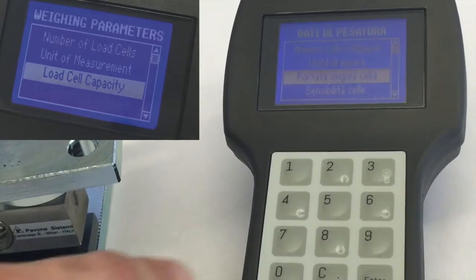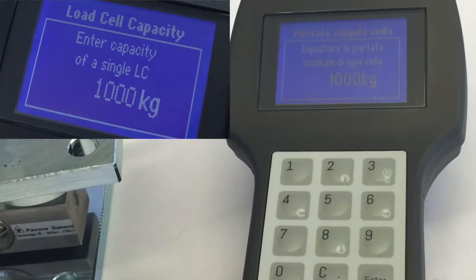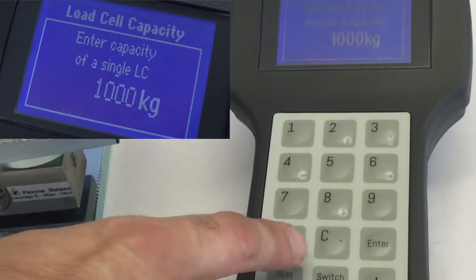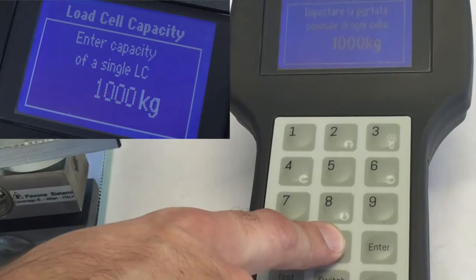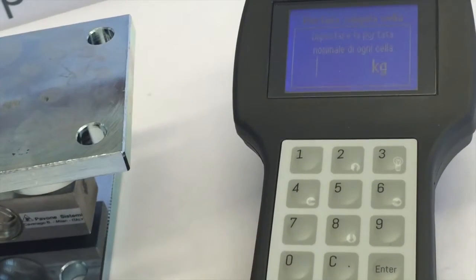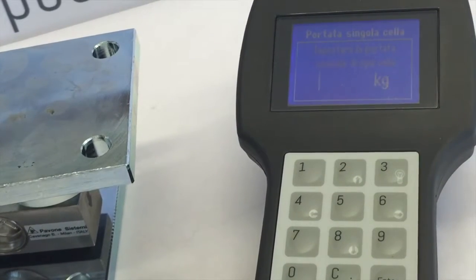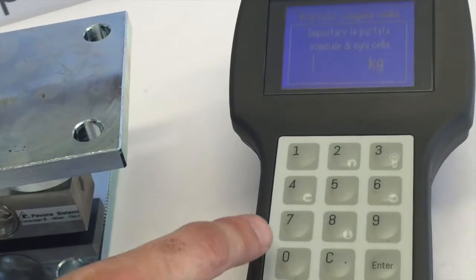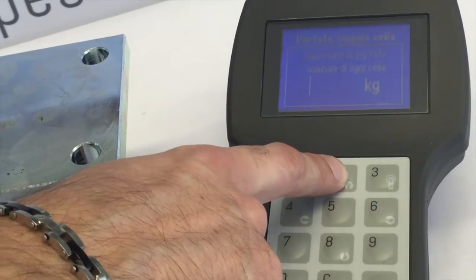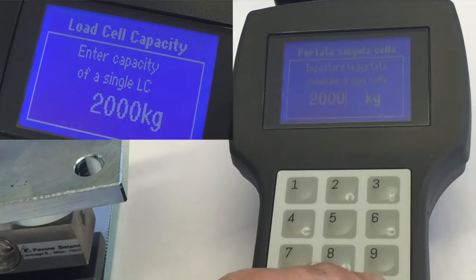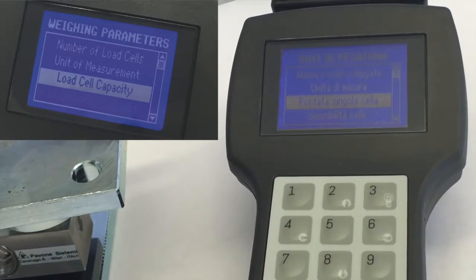Select Load Cell Capacity. With the right arrow, open the submenu. Delete the old value with C, and enter the new value. In this case, our cell is 2000 kilograms. Set the value on the numeric keypad and confirm with Enter.